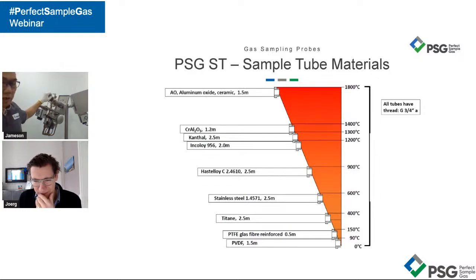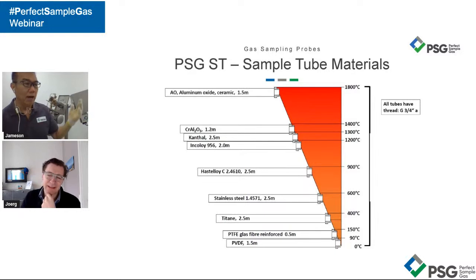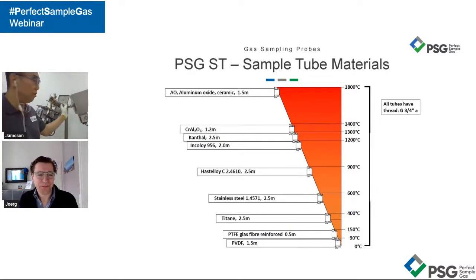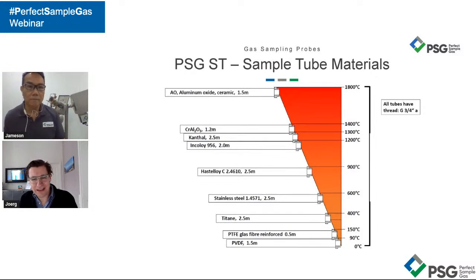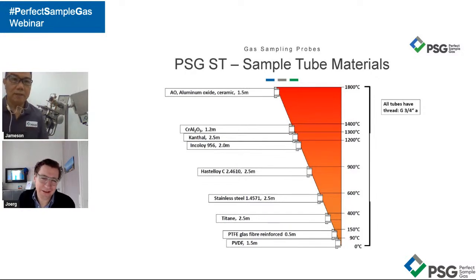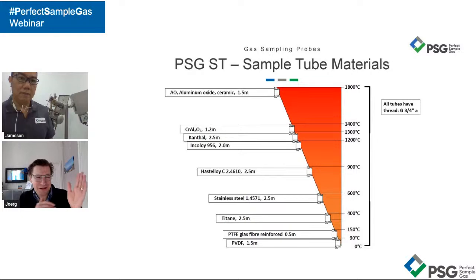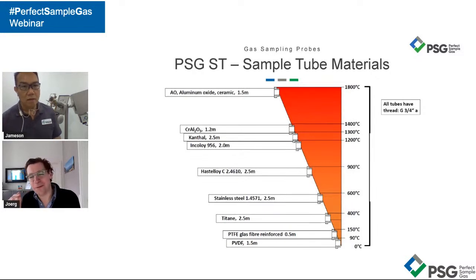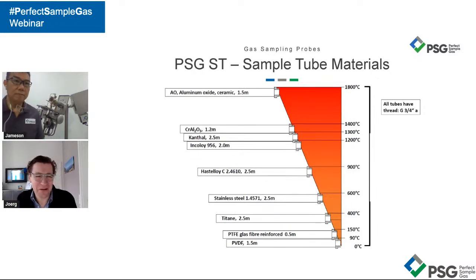Therefore, it is relatively important not only to choose the sample pipe material correctly, but also the positioning, and how far it has to be taken into consideration based on your flange design temperature. Yeah, all right, that's true. And I think this great overview also shows what the right material is for certain temperatures.